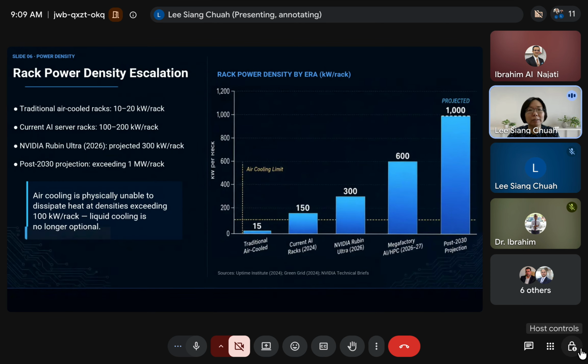Let's zoom out to the rack level, where the problem becomes even more severe. For many years, air-cooled racks operated at 10 to 20 kilowatts per rack. Today, AI systems are already at 100 to 200 kilowatts per rack, and next generation platforms like NVIDIA Rubin Ultra are projected to reach 300 kilowatts per rack. The key limitation is simple: air cooling hits a physical wall around 100 kilowatts per rack.